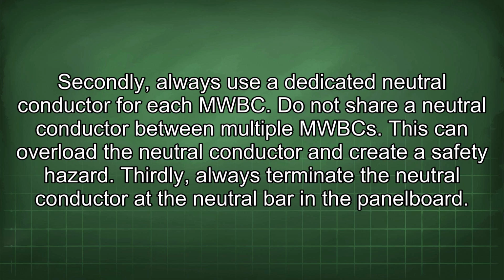Secondly, always use a dedicated neutral conductor for each MWBC. Do not share a neutral conductor between multiple MWBCs. This can overload the neutral conductor and create a safety hazard. Thirdly, always terminate the neutral conductor at the neutral bar in the panel board.